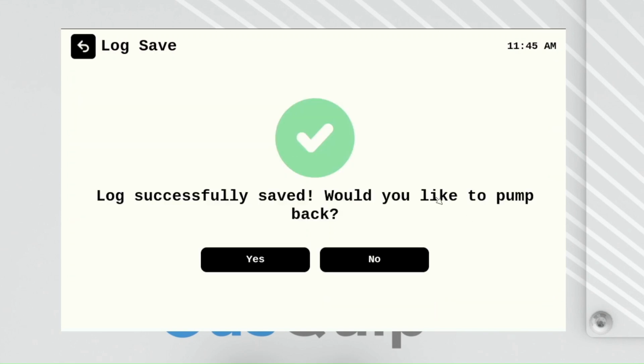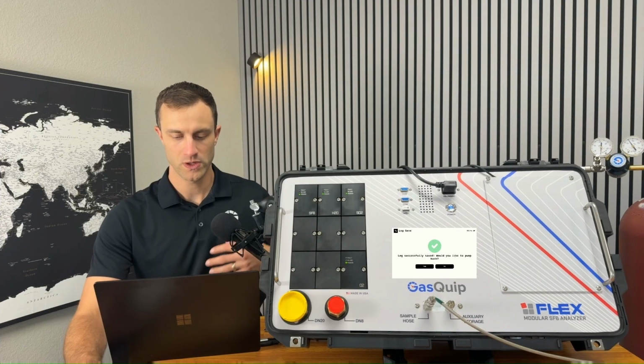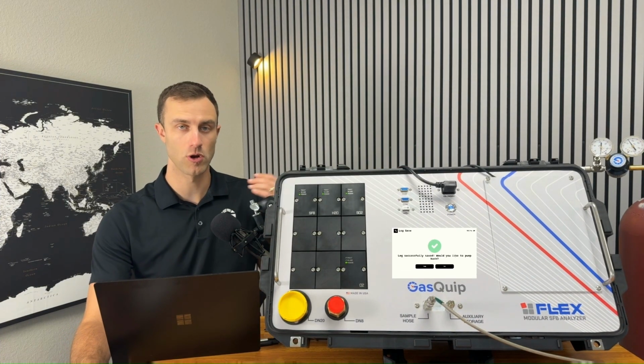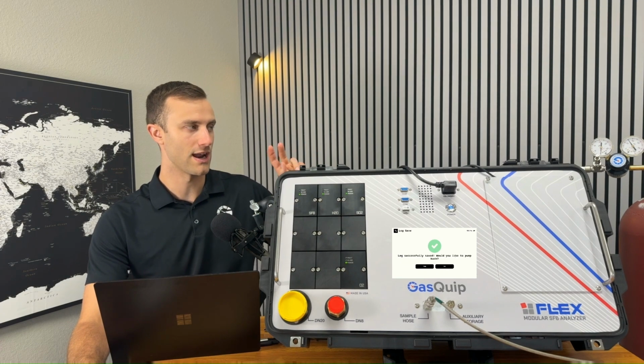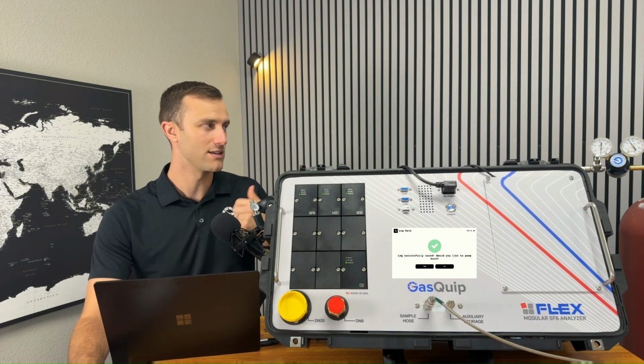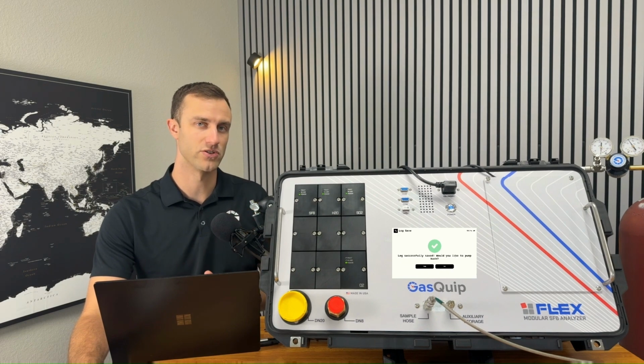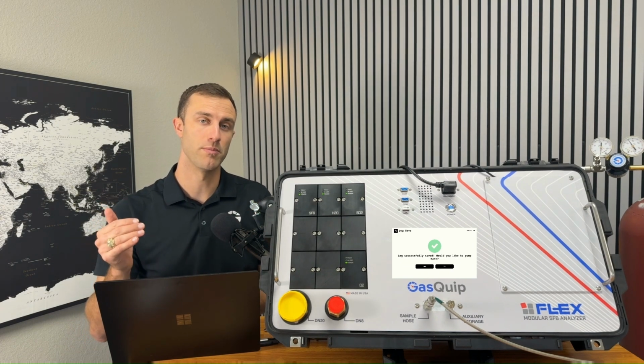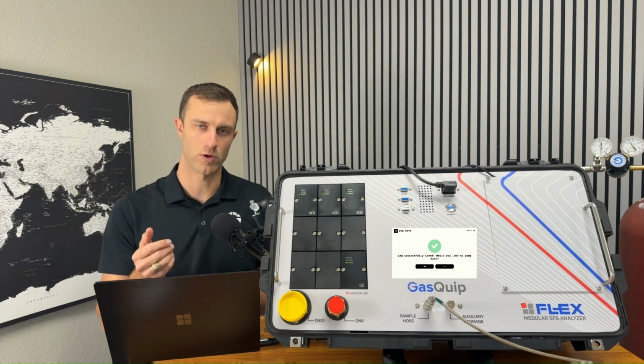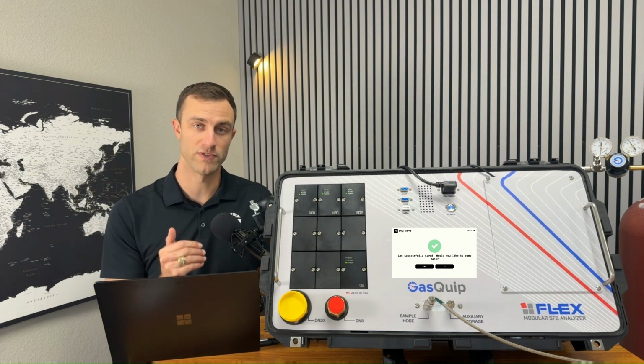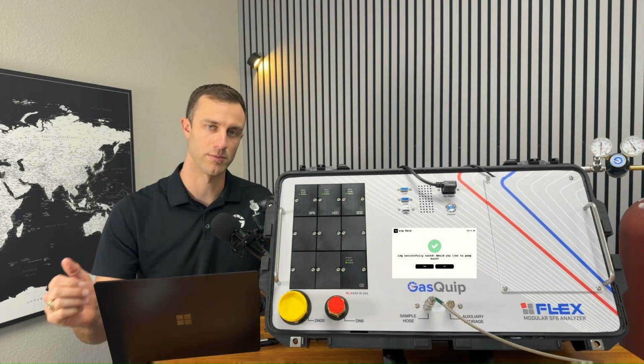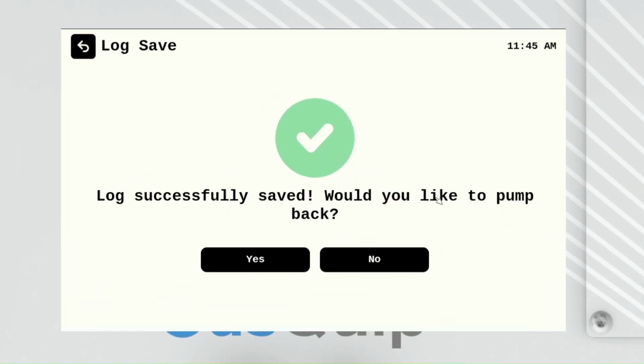I'm going to go ahead and save this, and it's going to say log successfully saved. Would you like to pump back? Since we are dealing with a regulator, we cannot pump the gas back through our regulator for two reasons. One being that our regulator has a check valve, and the second being that our actual gas cylinder is too high pressure, so you can only pump back into a gas reservoir or a cylinder that is below 150 psi, because that's what the internal pump can handle. So we won't be able to pump back into our bottle, so we'll say no for now.